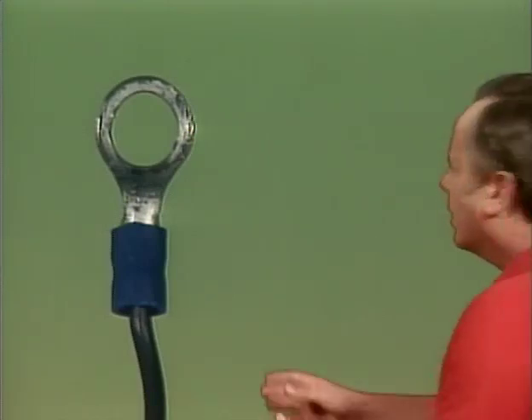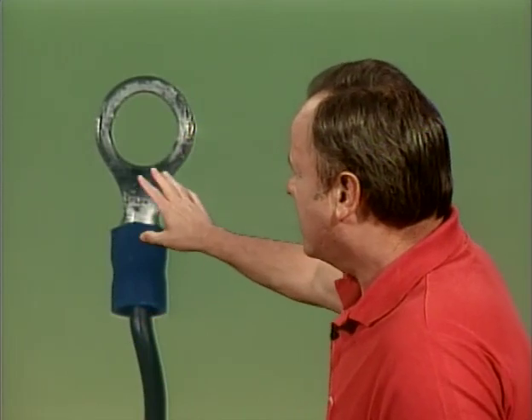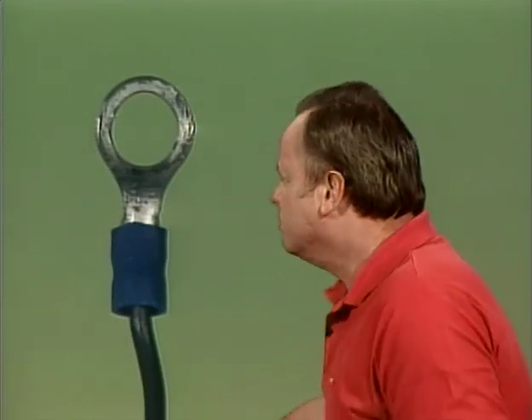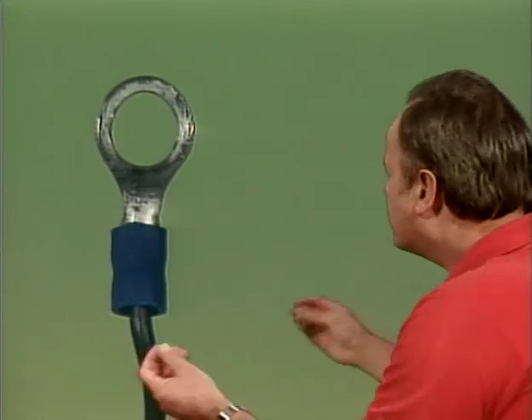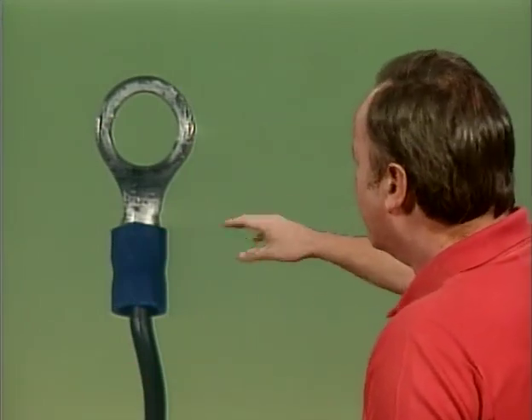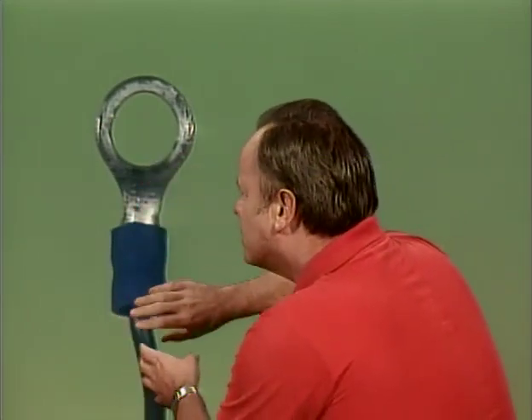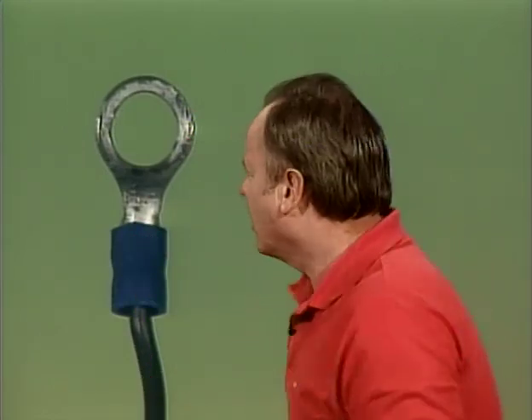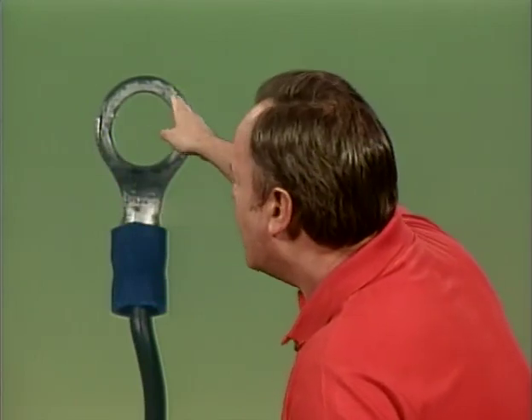Let's talk about putting electrical terminals on the end of a wire like this. And this is an example of an electric wire terminal. In addition to providing good current carrying capabilities, these terminals must be designed to prevent circuit failure due to disconnection, due to coming apart. So you've got to have them designed so they don't come apart and disconnect the circuit.